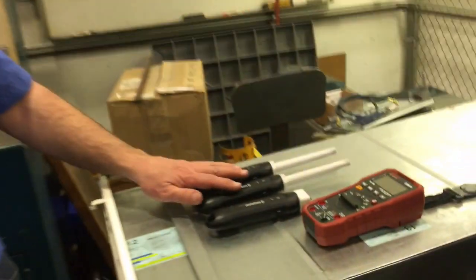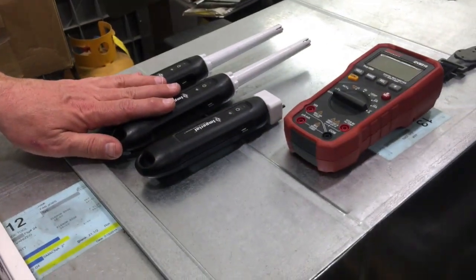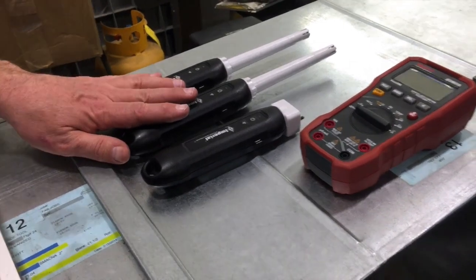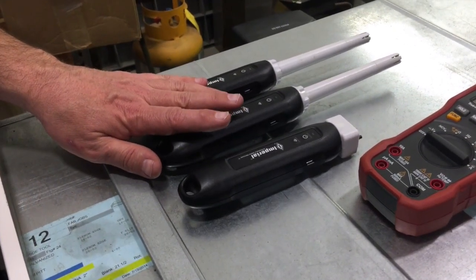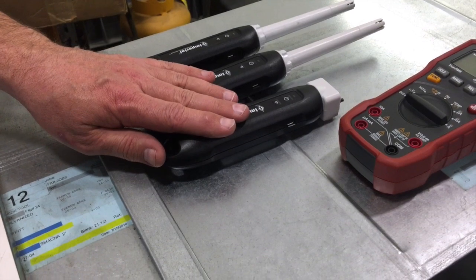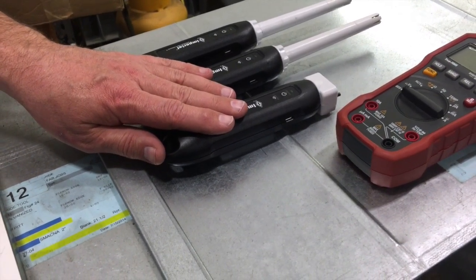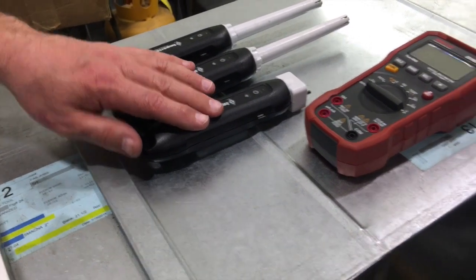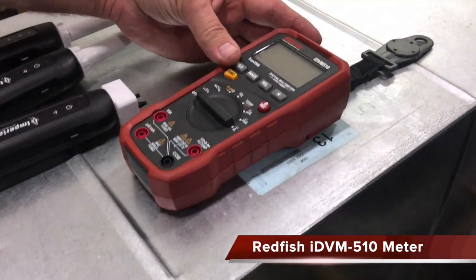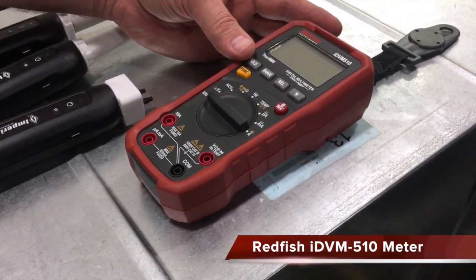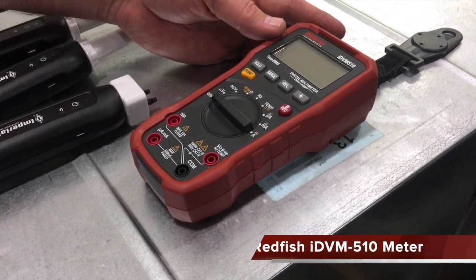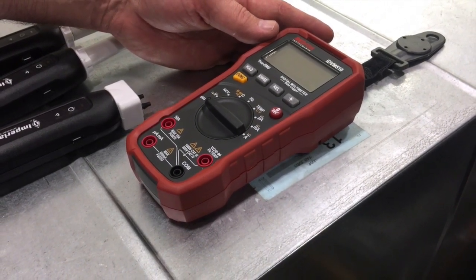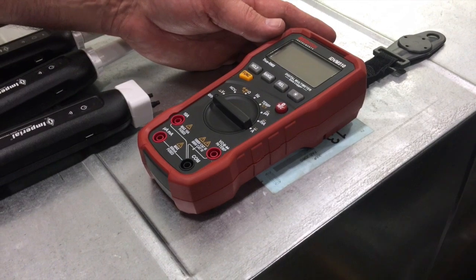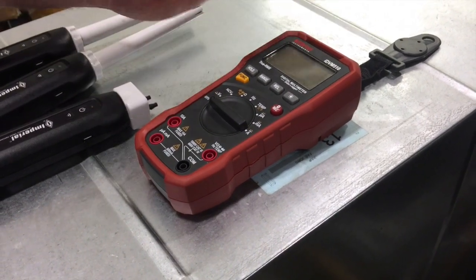So today what I've got out here is a couple of temperature relative humidity sensors. These are going to get me return air, wet bulb and dry bulb, supply air, wet bulb and dry bulb. I have our new 921N manometer so we can get return static, supply static, and total external static. And then I have the newest addition to our family here, which is the Redfish meter, the IDVM510. And we're going to use that product to get voltage and amperage right into the iManifold report as VeriFied readings. This will cut a tremendous amount of time of fat fingering in readings. I think you're going to find this pretty interesting.